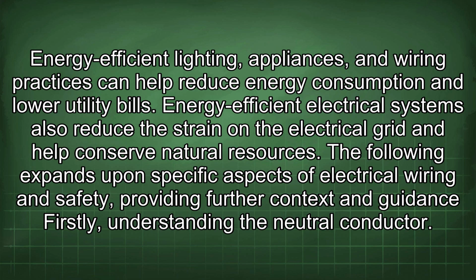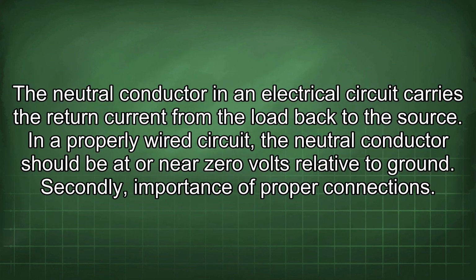Firstly, understanding the neutral conductor. The neutral conductor in an electrical circuit carries the return current from the load back to the source. In a properly wired circuit, the neutral conductor should be at or near 0 volts relative to ground.